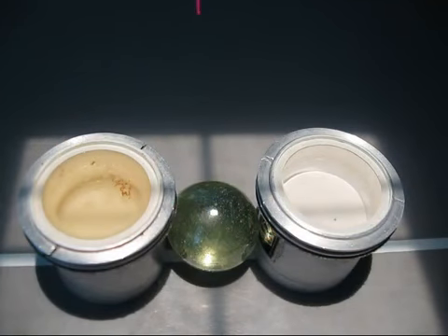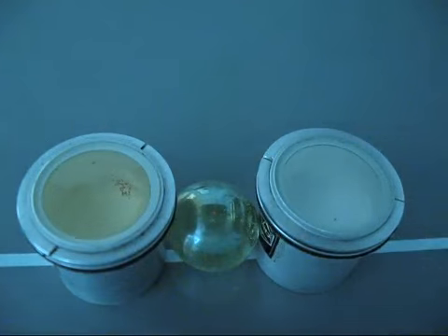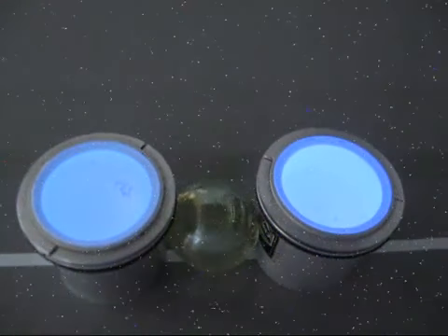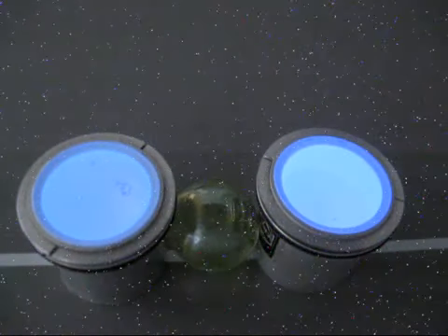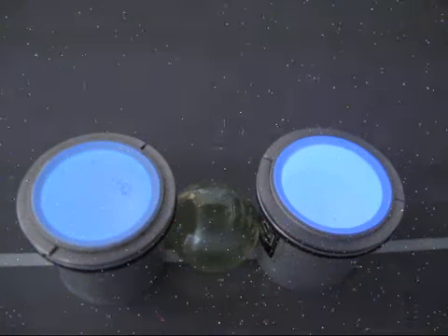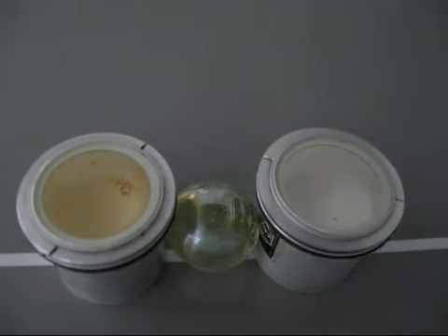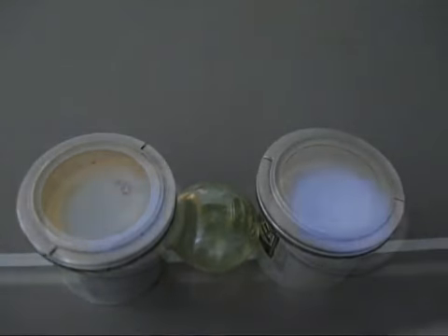So here we go again with a different angle. I'm adjusting the field of light again, which will be the field of primary X-rays. The other stuff you will see on the camera is just stray radiation, which inevitably occurs. And here we go, X radiation, and you can see the intact crystal on the right is much brighter than the one on the left. So yeah, as you can see, scintillation crystals are really sensitive to humidity, and you should protect them from it.